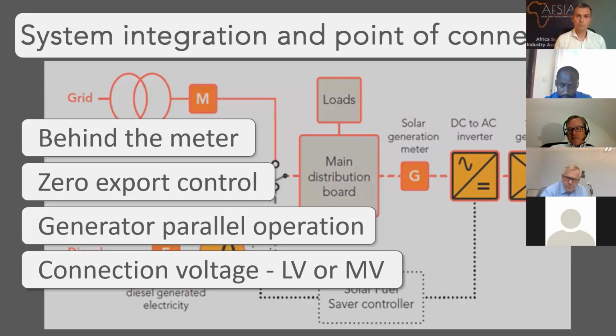Now, when we talk about grid parallel or grid-tied inverter systems, they will normally switch off when there is a power failure for safety reasons. I'm not going to go into the technical side of that, but with the inclusion of a generator parallel system, generator fuel saver controller, for example, you will be able to accept the power from the solar system in parallel with the generators. For Mombasa Airport, this was something we did include, so we had all of these functions.